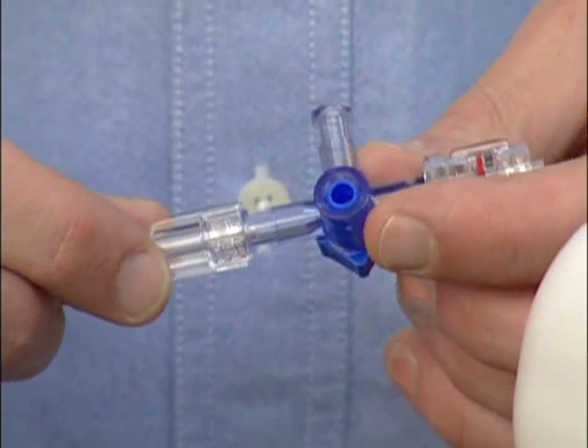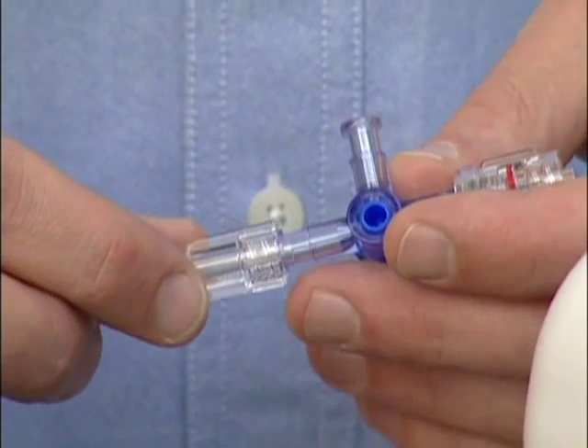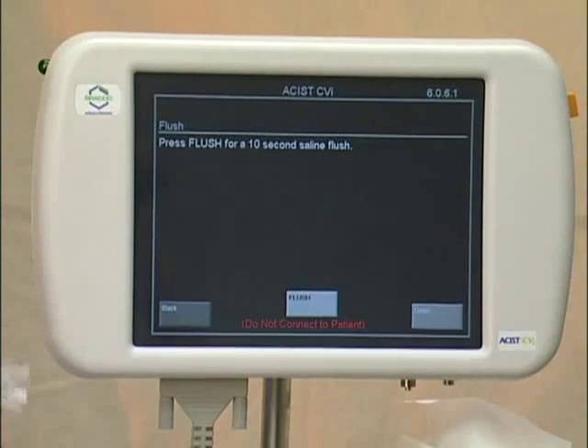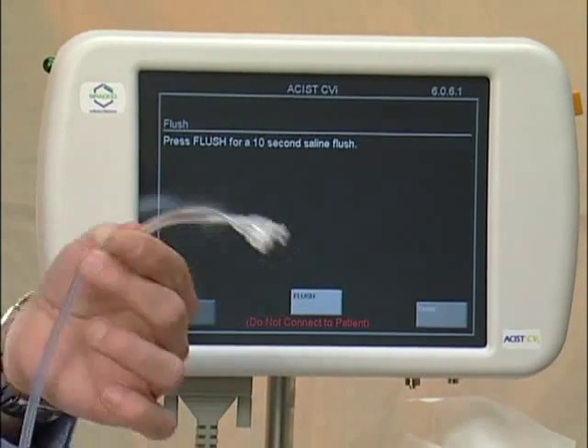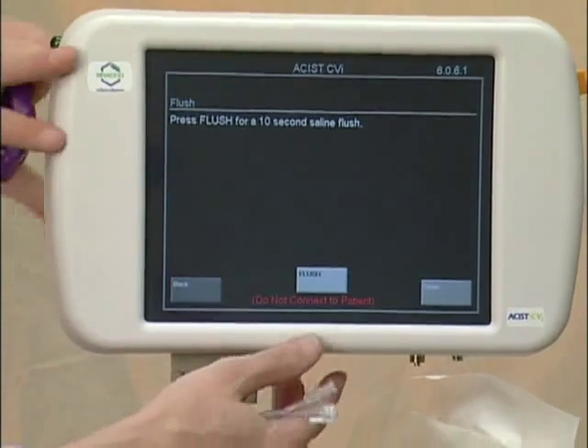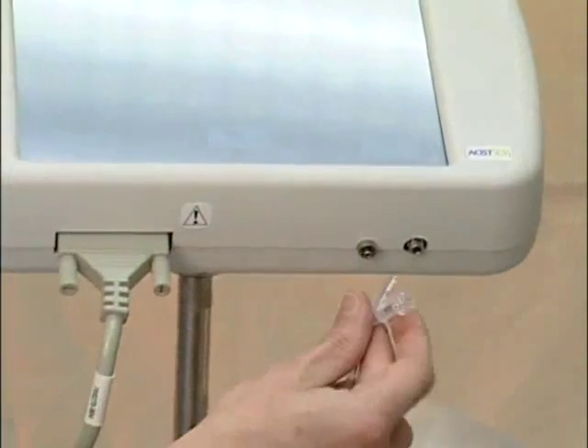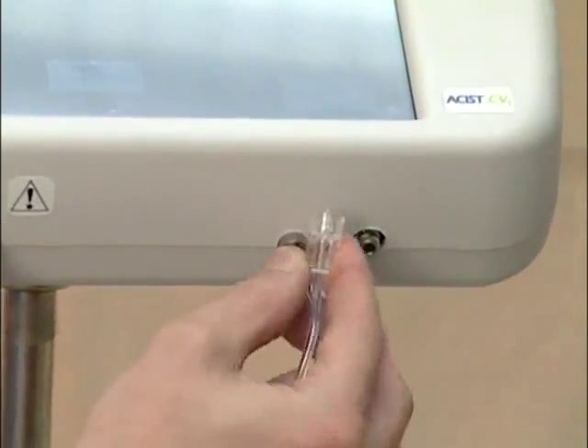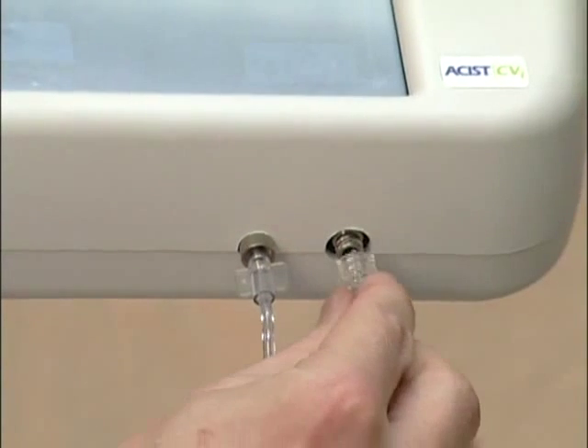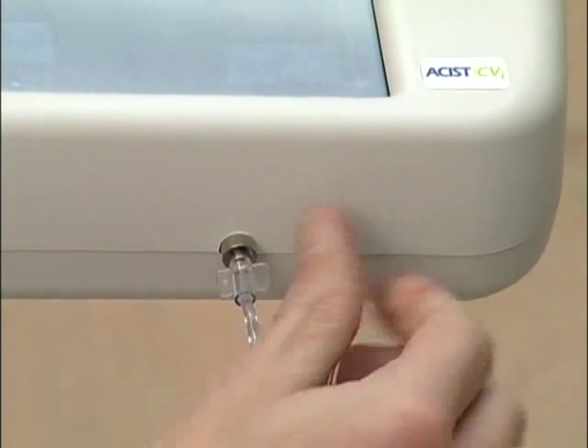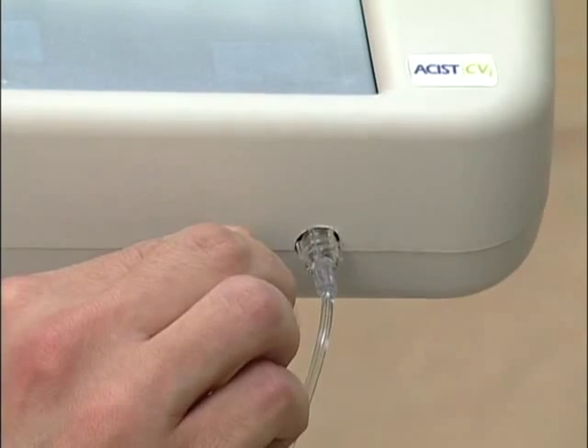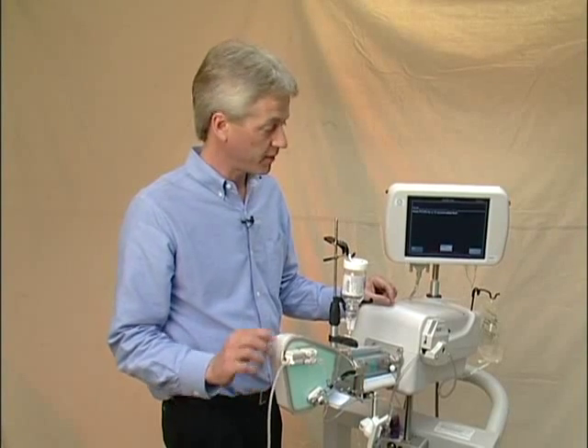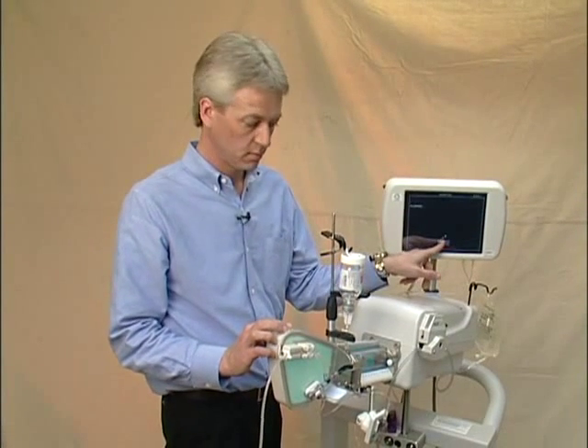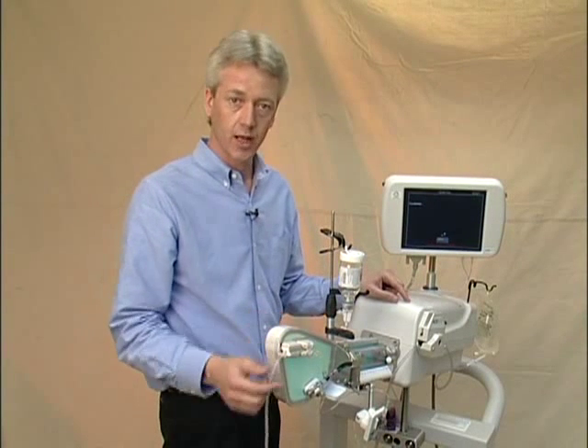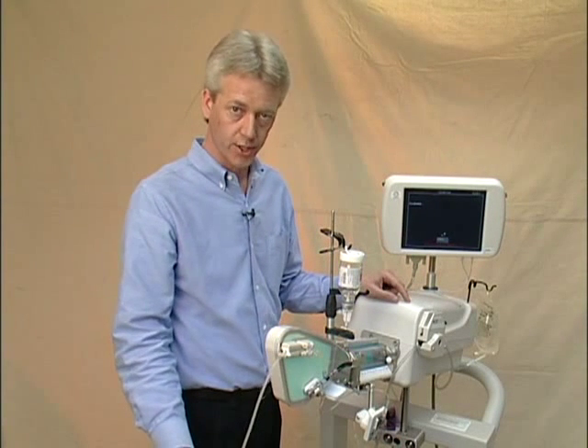So the physician will connect the stopcock, make sure it's a tight connection, and then we'll begin the flush sequence. The hand controller is handed off by the physician to an unscrubbed technician, and they will make the luer connections at the bottom of our hand controller. You have a male and a female luer, so they cannot be reversed, and make sure they're nice and tight. The high pressure line is then flushed by pressing the flush button, allowing saline to completely flush out our high pressure tubing.